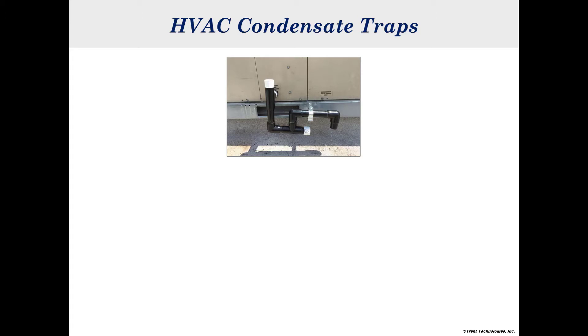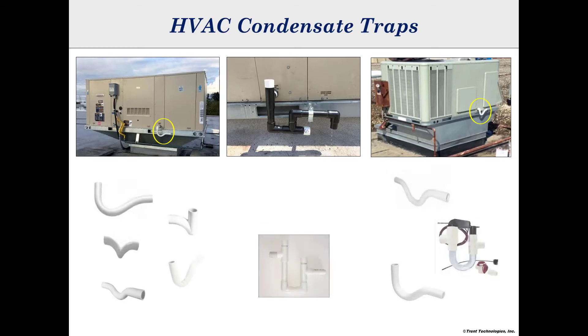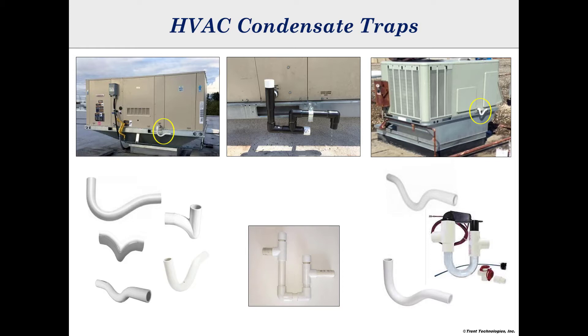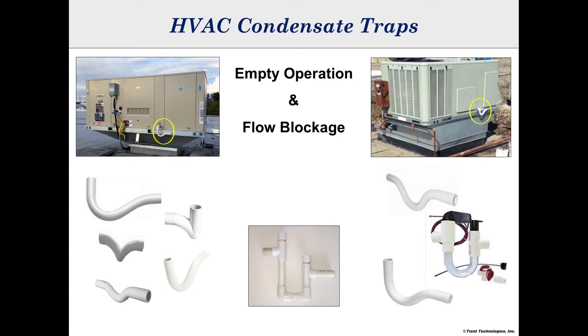Condensate traps for HVAC drain systems in all shapes and sizes are available from supply houses and field fabricators with little or no knowledge of pressure conditions and condensate flow rates. This chart shows some of the types of traps available. Some are more prone to failure than others, but all, including the best possible geometry, are subject to failure as a result of frequent empty operation or flow blockage.